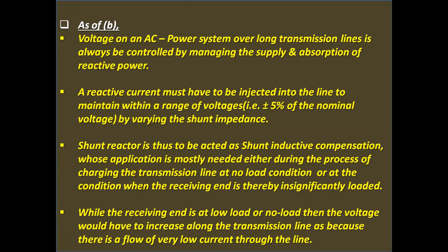As of the condition B, voltage on an AC power system over long transmission lines is always controlled by managing the supply and absorption of reactive power. A reactive current must be injected into the line to maintain voltages within a range, that is plus or minus 5% of the nominal voltage, by varying the shunt impedance.